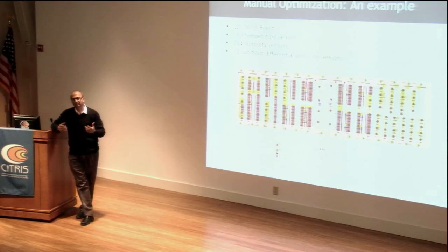The part that becomes difficult is because when you go to these data centers, most of them are organized in a fairly non-regular way. That is, the way they are organized, or the way the air flows, or the way you have anomalies in the data center because the data center hasn't been organized. It becomes a completely arduous task, because what you're doing is going through the data center one by one, row by row, rack by rack, trying to make sure that there are no airflow anomalies in the system.